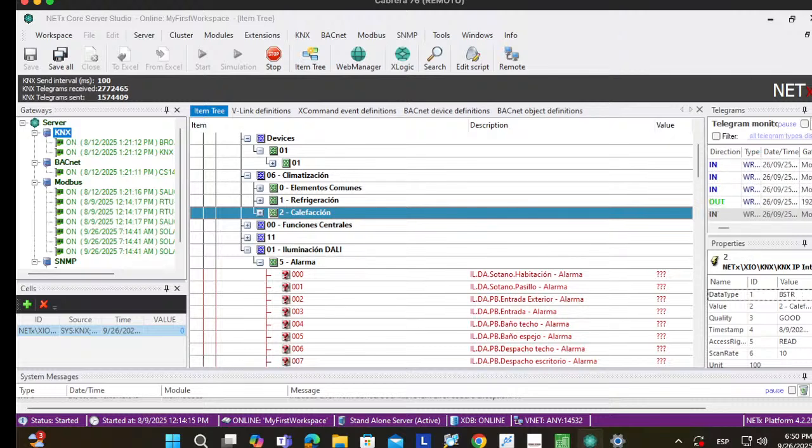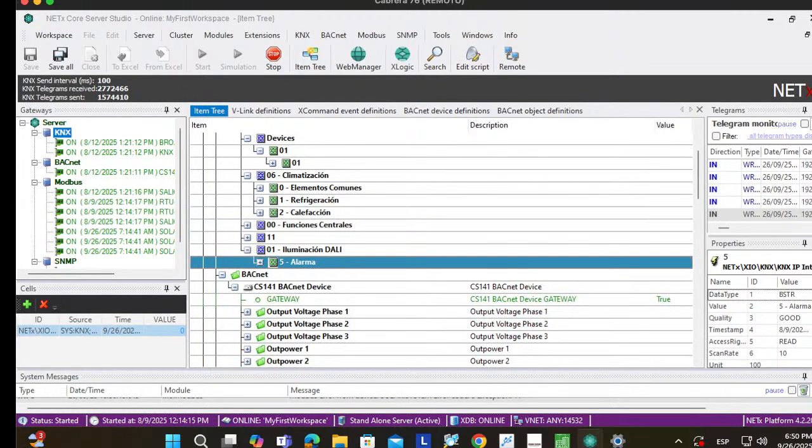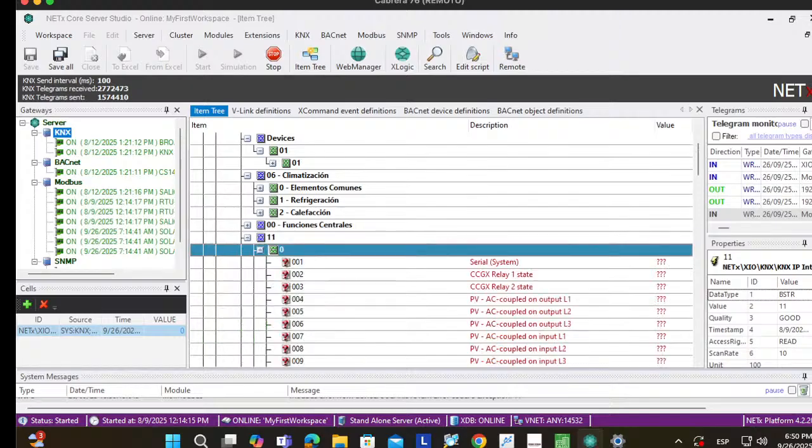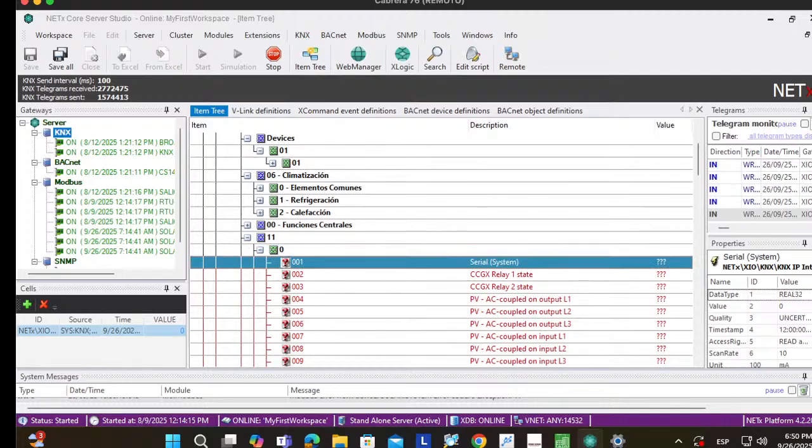Okay, good. So I have here KNX, a lot of KNX devices and KNX functions here as well. For instance, there is no one talking to this group address, so that's why it's like this. It didn't get information. The quality is uncertain, as you can see on the right-hand side, and the timestamp is this, read and write. Anyway, this item is not updated, so it's not good.